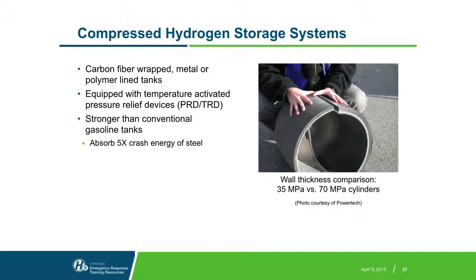So these are both a type 3, which is what's on the unit, an aluminum lined tank with the carbon fiber overwrap, and again at 35 MPa or 5,000 psi. Each tank is equipped with a thermally activated pressure relief device.